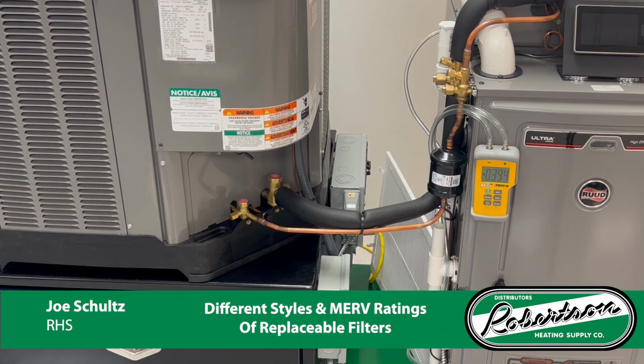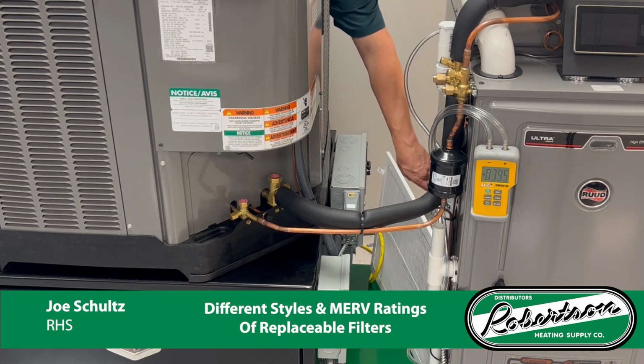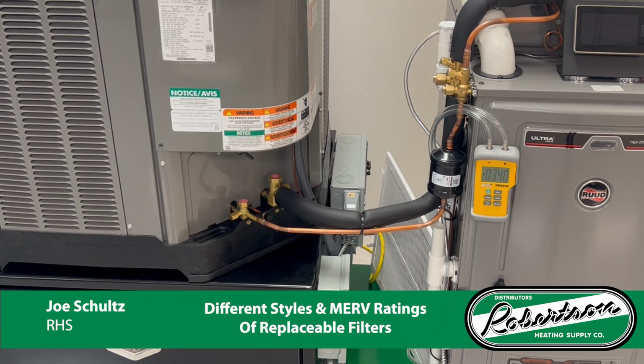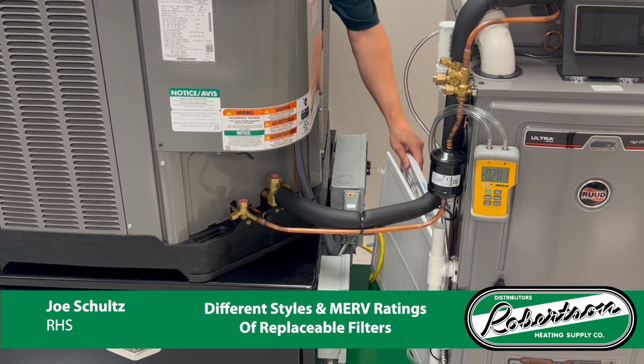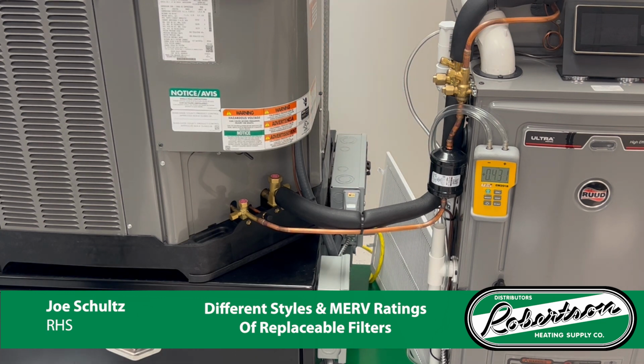So we moved from the Merv 10, and we will go up to the Merv 11 filter and see how we do. So you can see once again, as we move up into the Merv ratings, we are now in Merv 11. Our static has moved up to about 0.44 on average.